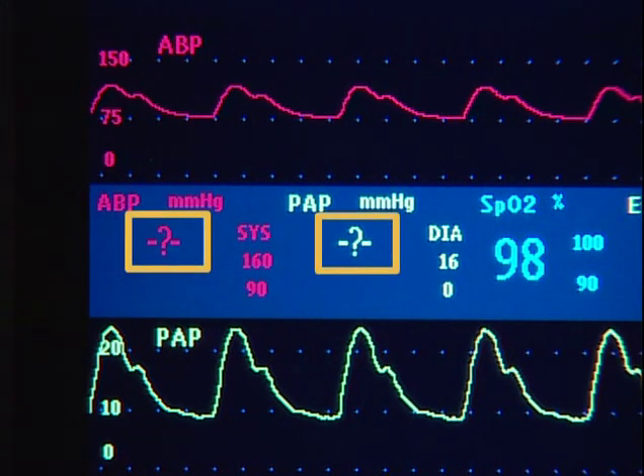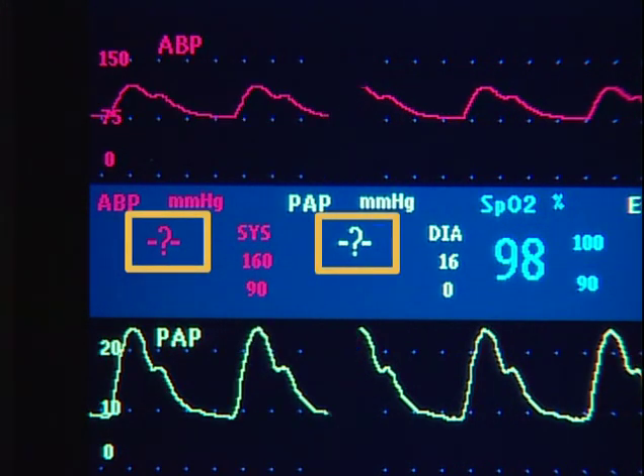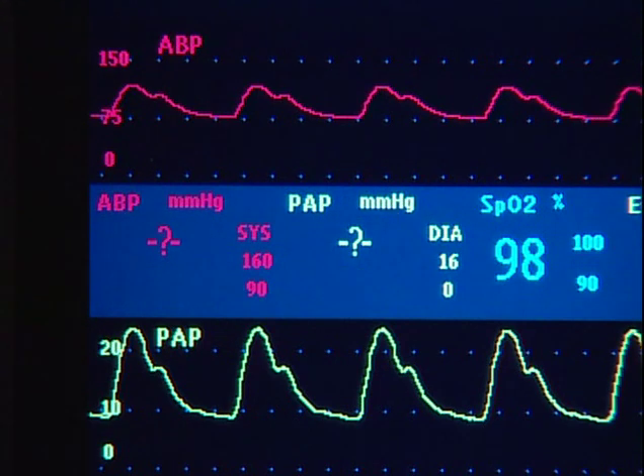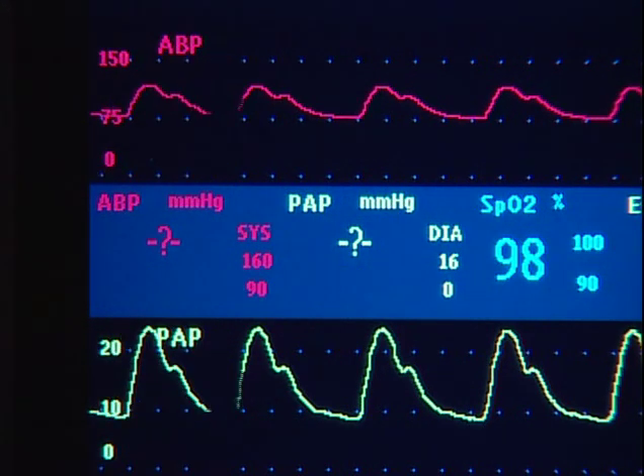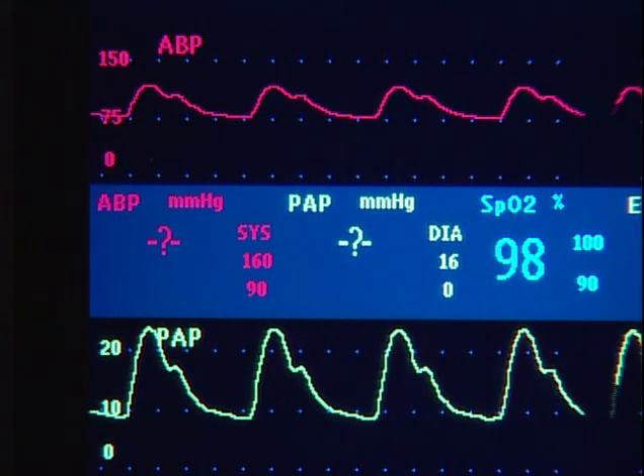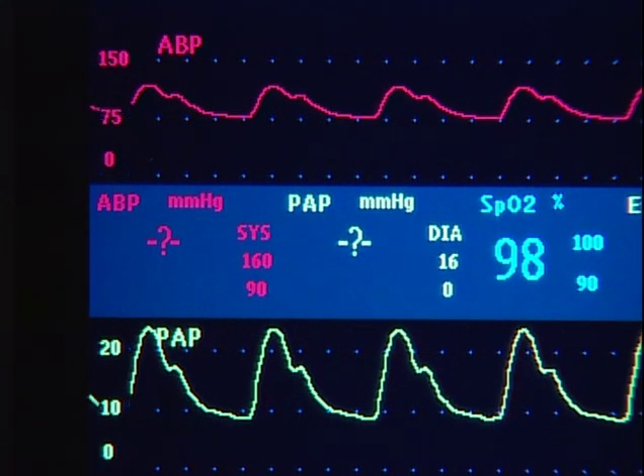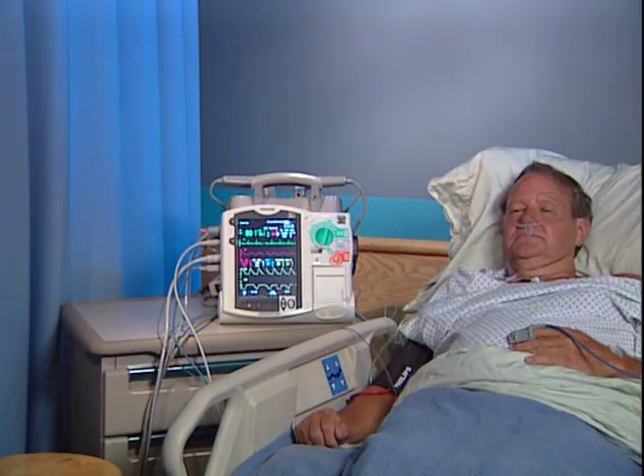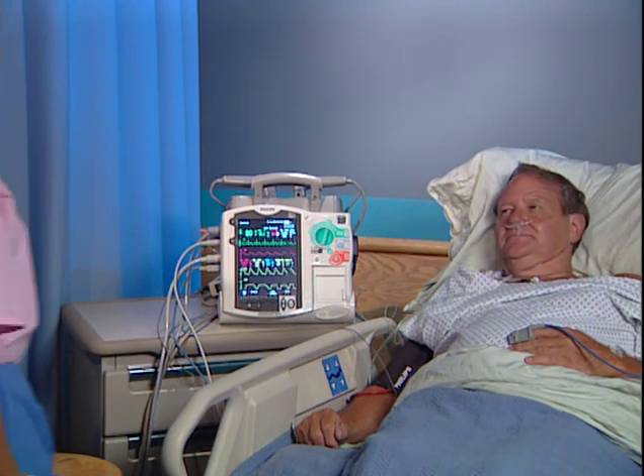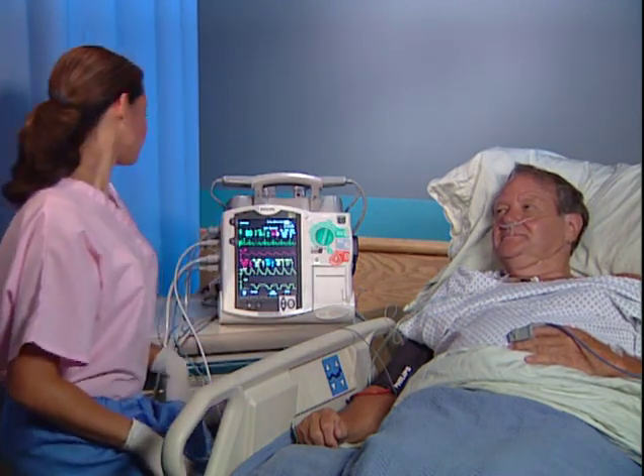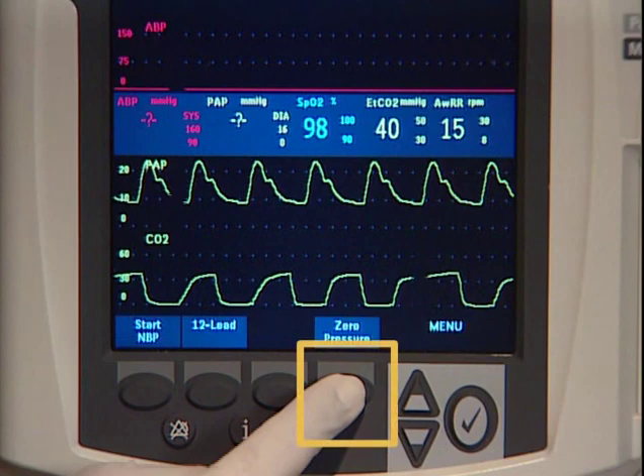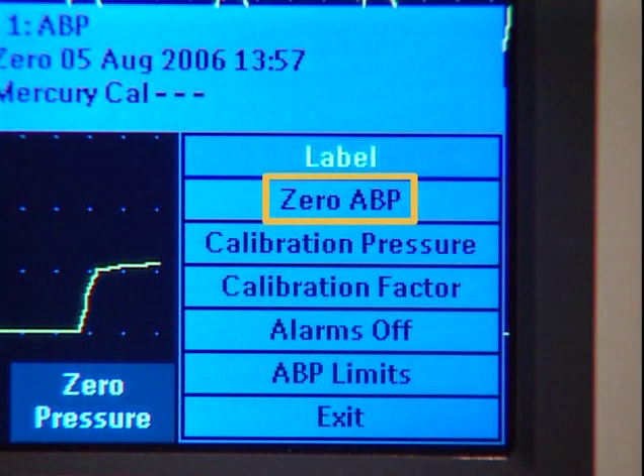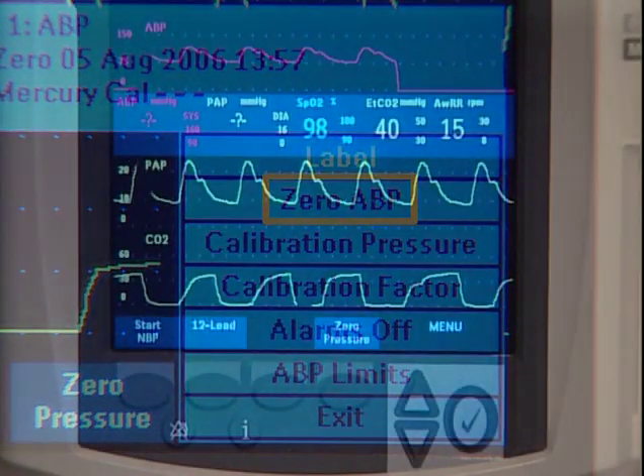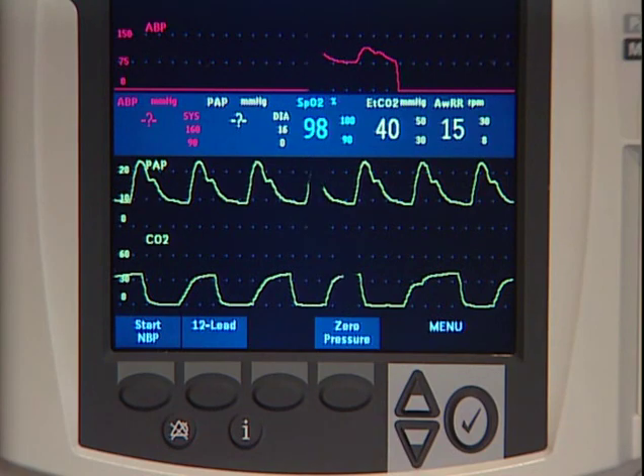This symbol indicates that you need to zero the transducer. Zeroing a pressure channel should be done according to your institution's policy, and for circumstances such as after moving a patient or using a new transducer. There are 2 ways to perform a zero with a HeartStart MRx: using the zero soft key while in monitoring mode, or using the zero function accessed through the menu Select button. We'll demonstrate using the zero soft key.